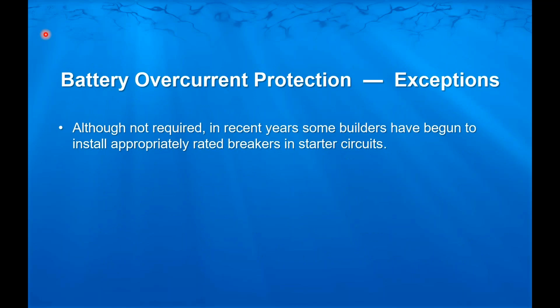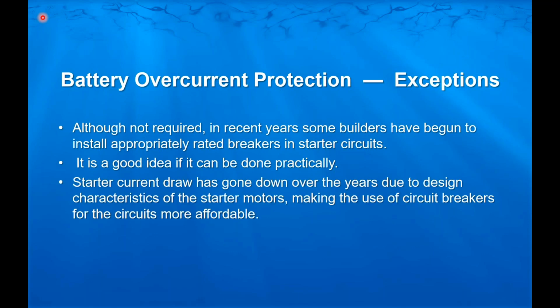Although it's not required, as we discussed, in recent years some builders have started using appropriately rated breakers in their starter circuits. If you can do it practically, it's a good idea. There's no reason not to do it. It's just not required. That's because starter current draw has gone down because of better design characteristics of the starter motors, and it makes the use of circuit breakers for those circuits more affordable. That's mainly the issue as to why they're not required, is because coming up with an available breaker or fuse that will survive the current inrush of a starter is not practical in almost all applications.